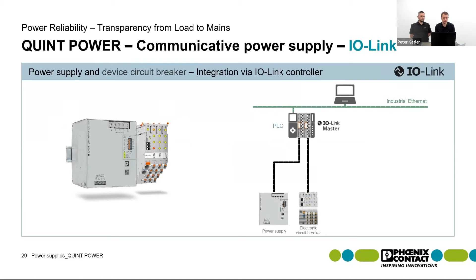And also, as Peter explained, we have a CAPAROC module with IO-Link, which you can directly connect together. In case of the UPS, it's done in a quite different way: the power supply itself acts as a gateway for the UPS and the battery, collecting all the data and providing the information to the IO-Link master.